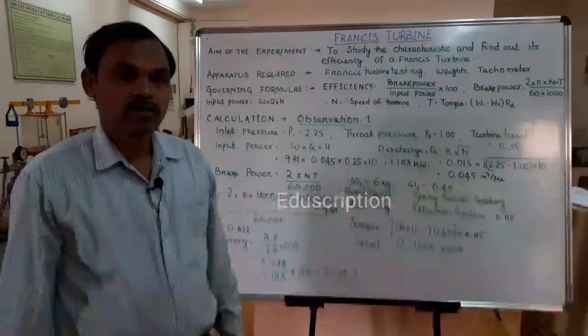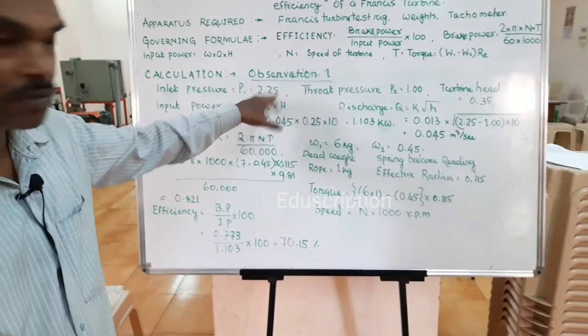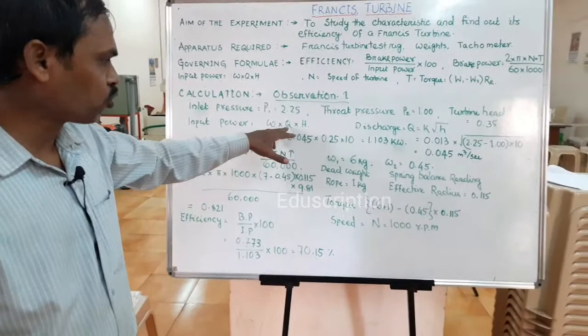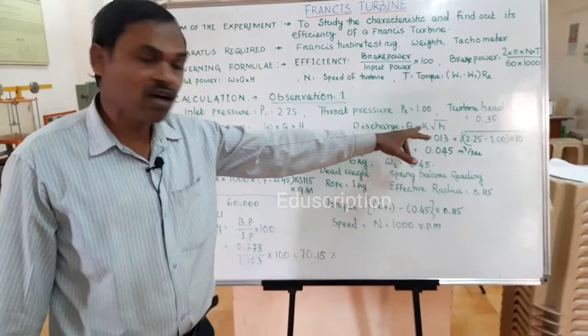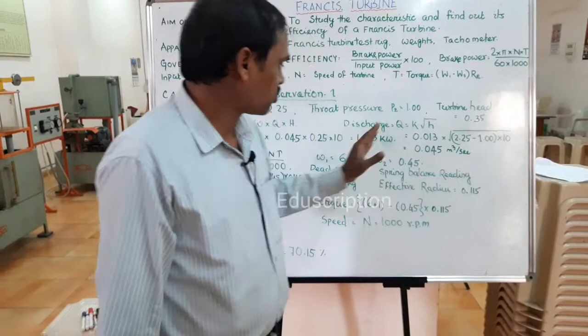Next we move to the calculation part. Initially we take inlet pressure as 2.25 kg per centimeter square, throat pressure as 1, and turbine head as 0.35. For the basic calculation of input power, that is W×Q×H, the discharge is Q = K × √(P1 - P2). The venturi constant K has a value of 0.013. When we convert P1 and P2 into head we multiply by 10, and finally the discharge is 0.045 cubic meters per second.